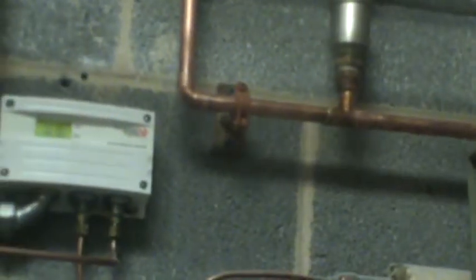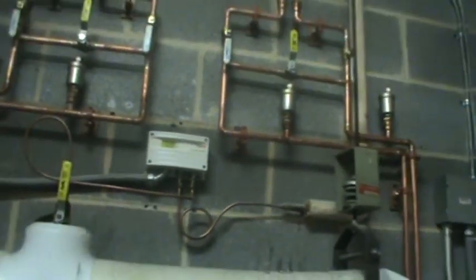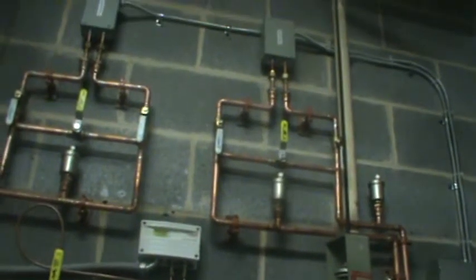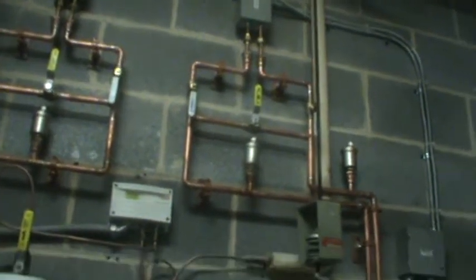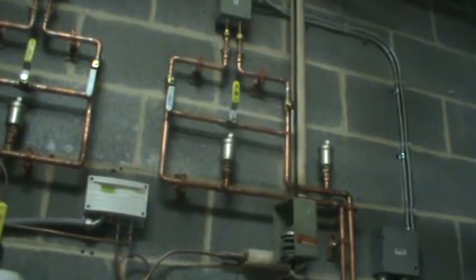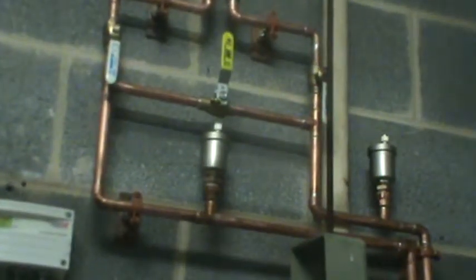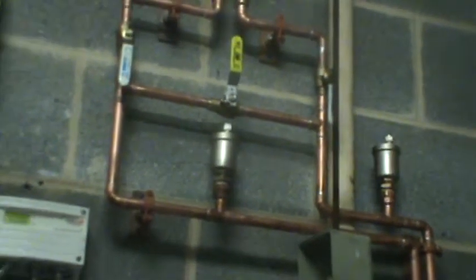Your pressure transducer basically just reads both suction and differential. What's the difference? It sends a signal to the drive telling how fast to go. Make sure your valves are kept open, except for your bypass. Make sure that's kept closed. Make sure the lines going to the system are kept open, or you get a really confused transducer and it tells the drive to do all kinds of weird stuff.